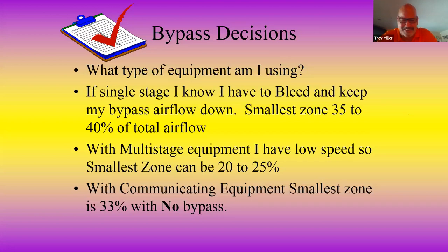Now, the answer is multi-stage equipment. Multi-stage equipment. It's beautiful because I have low fan speed. Now I can go down to 20 to 25% of the total capacity for my smallest zone. The neat thing about this is now we're into the master bedroom, master bath. And guys, that's one of the biggest zones in my mind. One thing we all do, we all sleep in our bedroom. We all want to be comfortable while we're sleeping. Everybody should, in my mind, have a thermostat in their bedroom to make sure they're comfortable for 1/3 of their life while they're sleeping. And this helps you with this here. But with multi-stage equipment, the low fan speed allows you to go down to that 20 to 25% for the smallest zone.